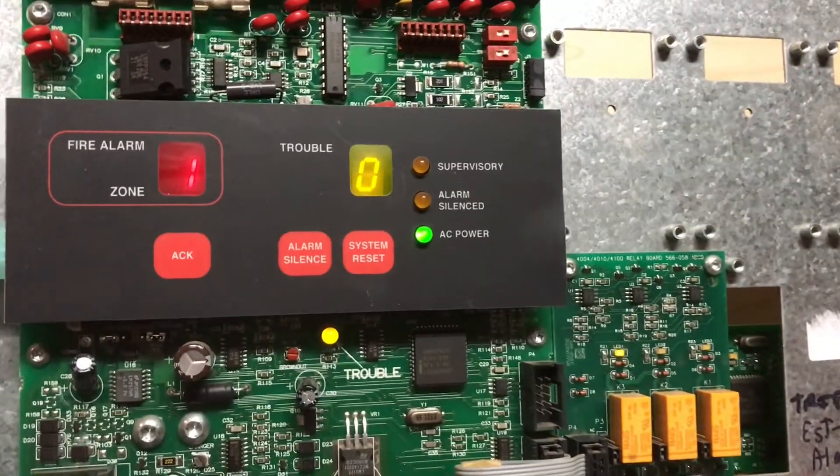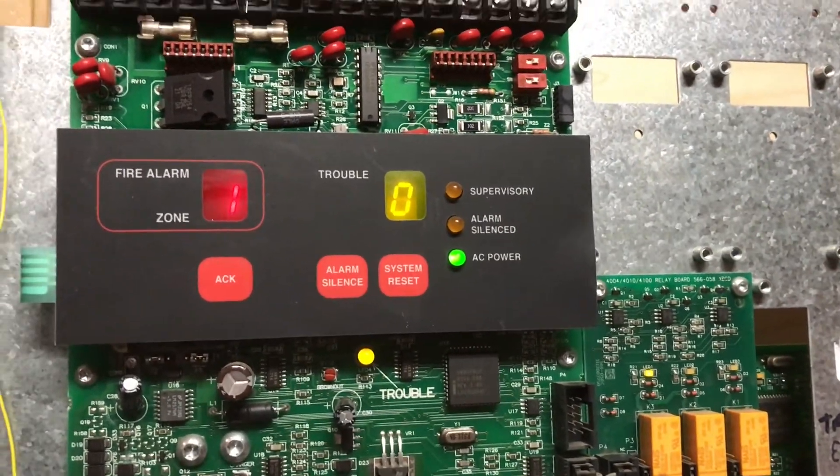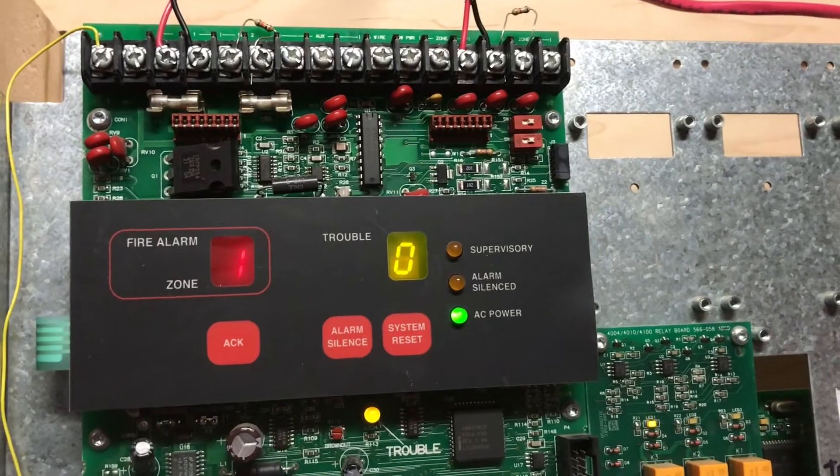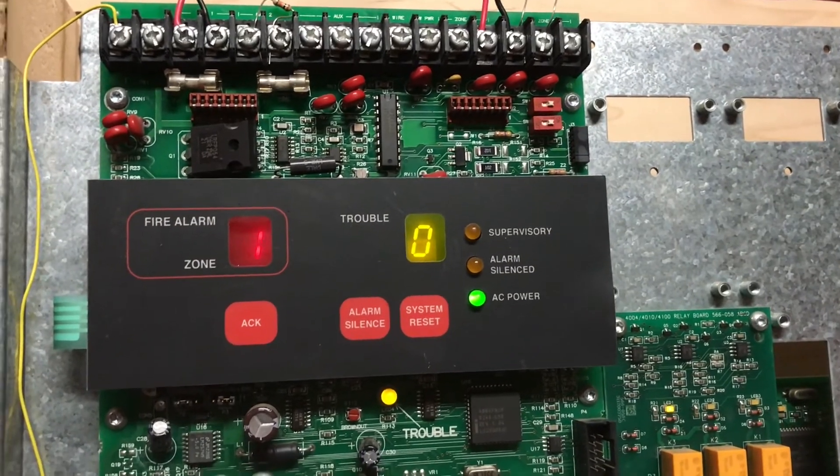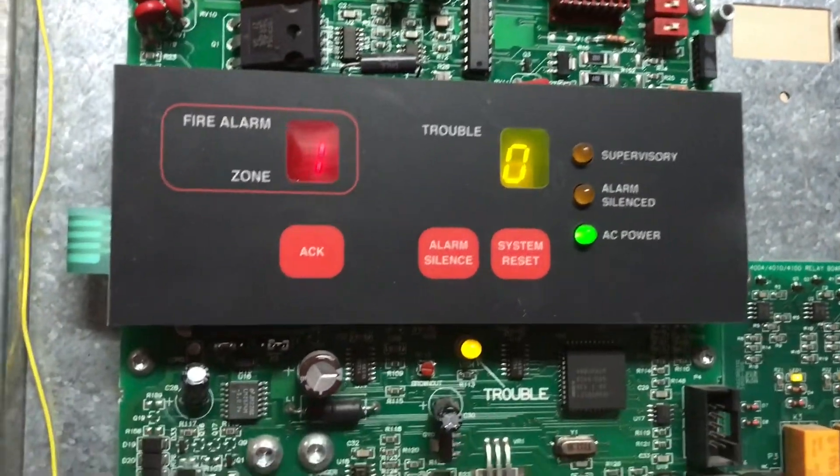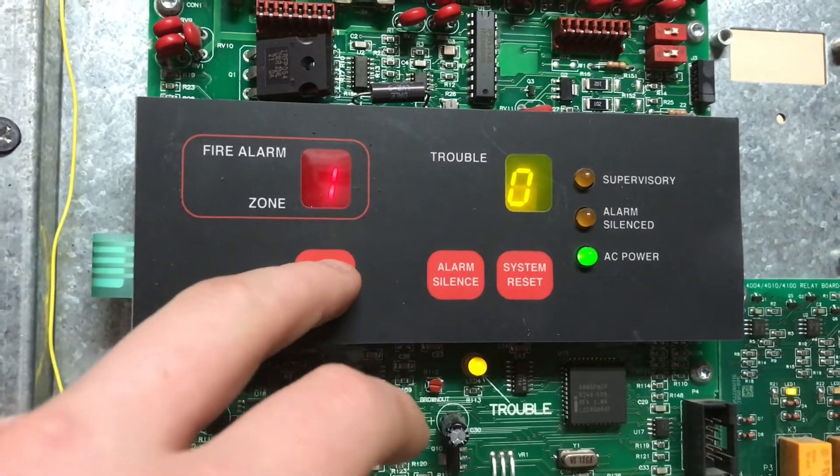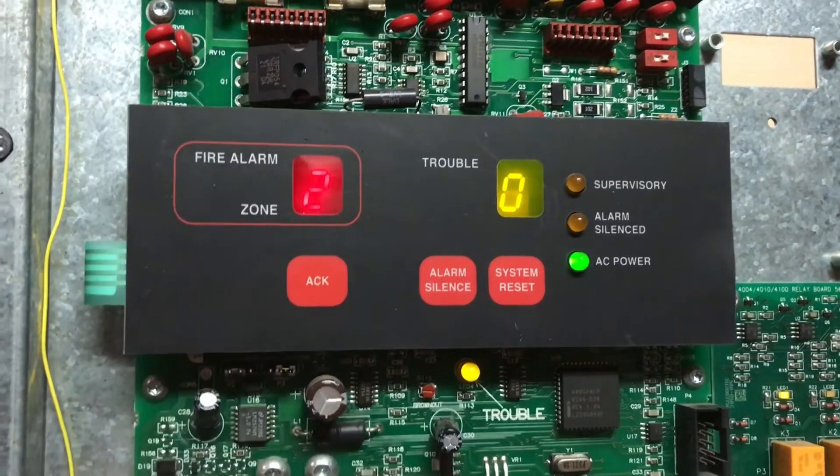Next option is to determine which zone is programmed as what. So, it can be programmed as either fire monitor, alarm verification, fire supervisory, trouble, or a style C contact zone. But, since I don't need any of that, let's move on.